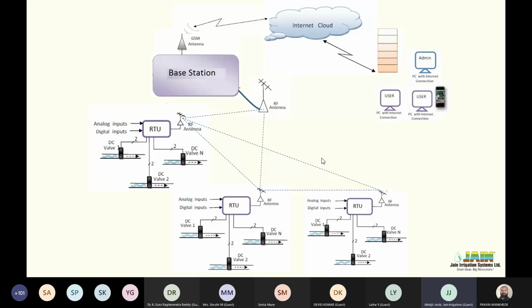So once the schedule is available with the RTU, even if communication fails for any reason—because in the field it's always possible the RTU may fail, or something happens, or GSM communication may break down suddenly in remote areas—even with no communication, the RTU still has its own schedule and can operate the valves as per the given schedule, unless there is a change.